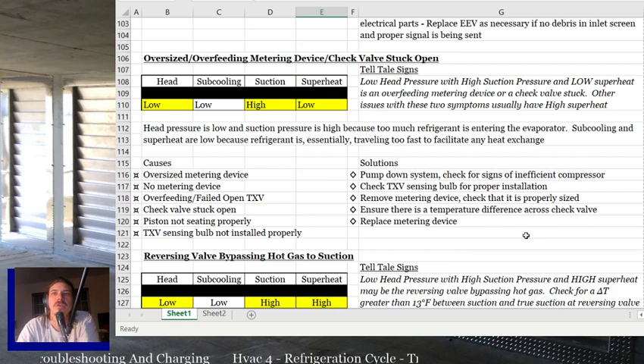If you have any of those issues, the signs are going to be low head pressure, low subcooling, but that's really irrelevant, high suction pressure, and low superheat. Basically, anytime you've got low head pressure and high suction pressure, you've got a small group of problems you can have, because it's not very often you have low head with high suction. It's kind of hard to pull that off. So you've got a very narrow group of about 3 problems you're usually looking for.